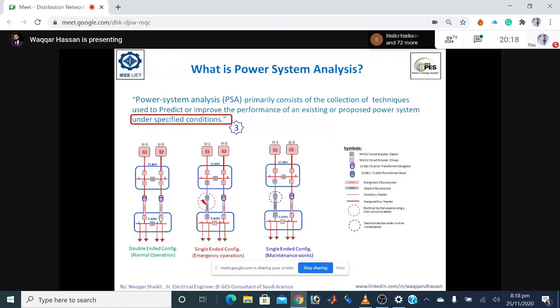Here's another example: a fault may happen on the secondary side of the transformer, causing an outage, and this transformer can get out of service. In this case, it's important to know how the other transformer will carry the load of the entire installation. So when doing the study, we want to make sure our system can operate with a single-ended operation. This is an emergency condition for any plant, and it's one of the scenarios to consider under specified conditions.